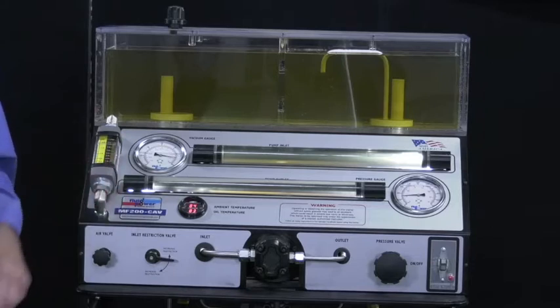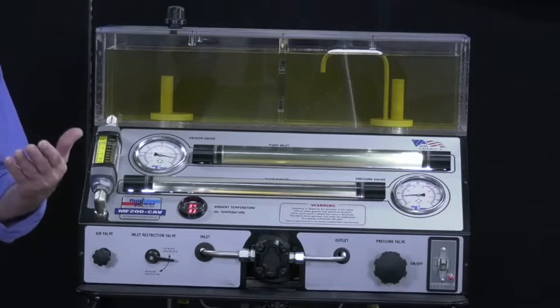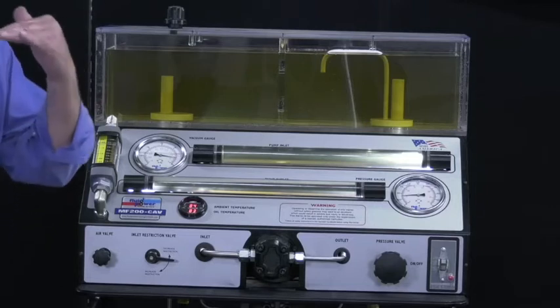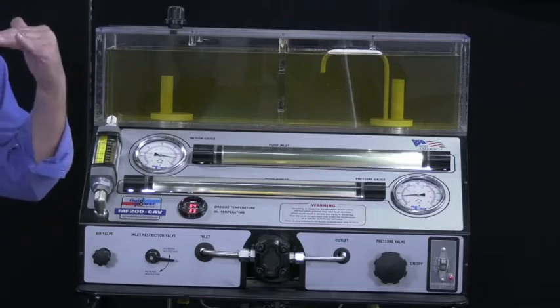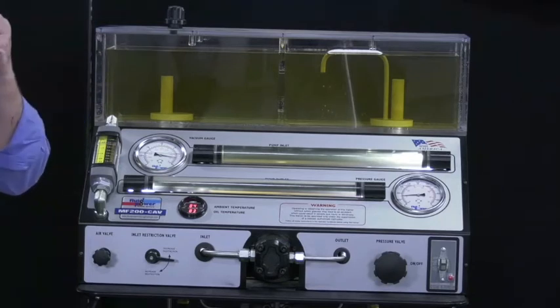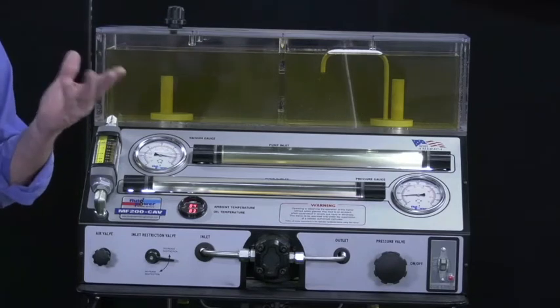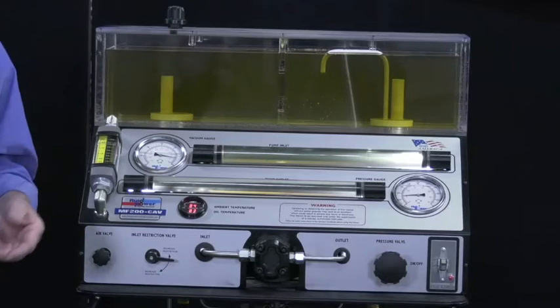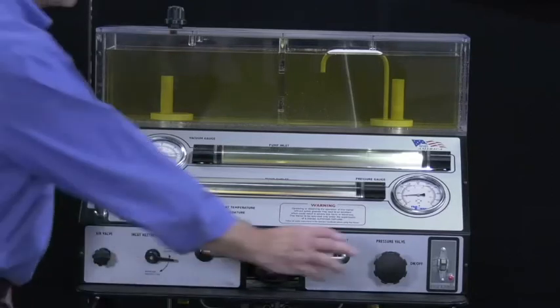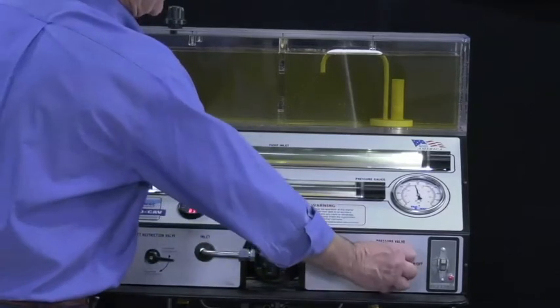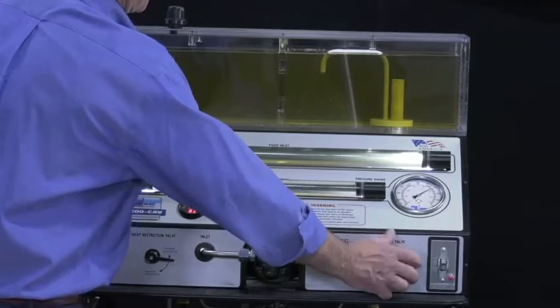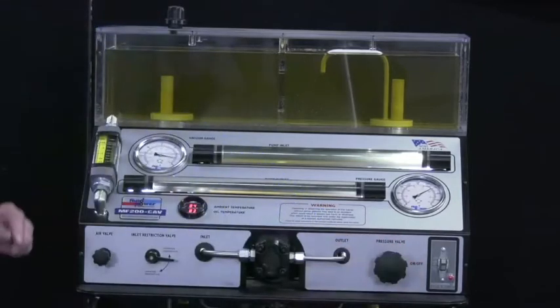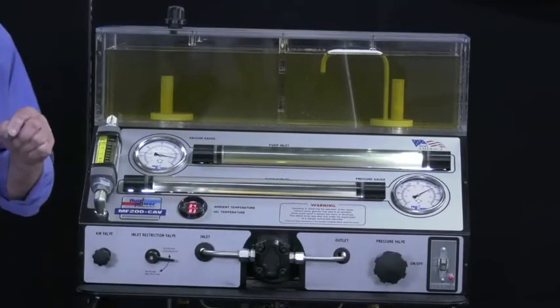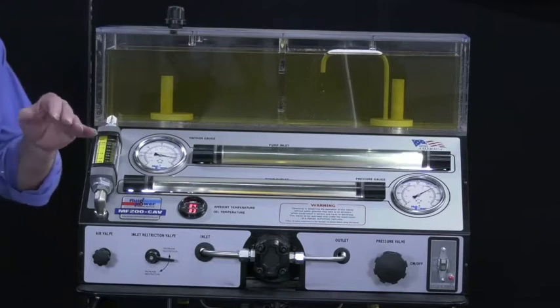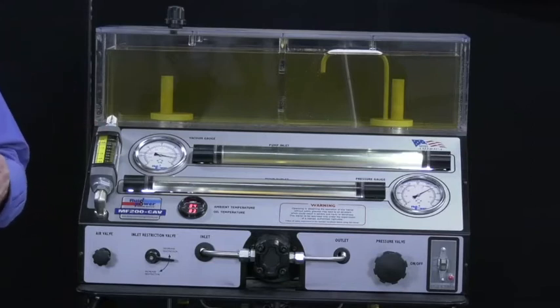So now let's go ahead and ramp the pressure up, because the noise of cavitation, of course, is set by how much pressure you have in the system, because the higher the pressure, the more intense the implosion, and therefore the more it's likely to scream. I'm going to go up to 700 psi. All right. And now I'm going to replicate a plugged screen.